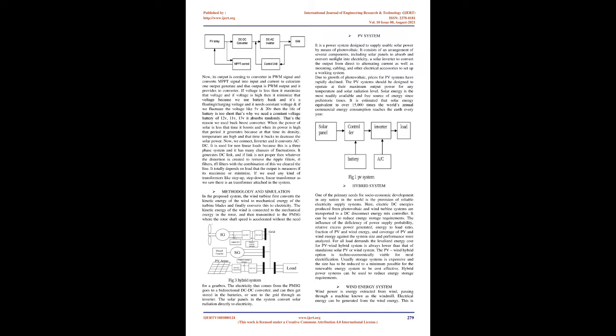The control of solar photovoltaic systems has recently attracted a lot of attention. The perturbation and observation, P&O, MPPT algorithm is commonly used, due to its ease of implementation. It is based on the observation that if the operating voltage of the PV array is perturbed in a given direction and the power drawn from the PV array increases, which means the operating point is moving towards the MPP, so the operating voltage must be perturbed in the same direction. A small wind generation system uses wind speed estimation and PI control for maximum wind power extraction.